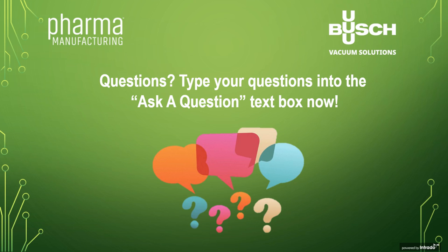Sure, I'll go ahead and take that. So the simple answer is yes, potentially. It depends. Part of what a separator might do when you have an inlet, what we call knockout pots, is you have the tangential kind of flow. Essentially, if air comes in mixed with water, it's hard for it to go through the physics of coming out the top. So you could use a receiver to get rid of some of that.